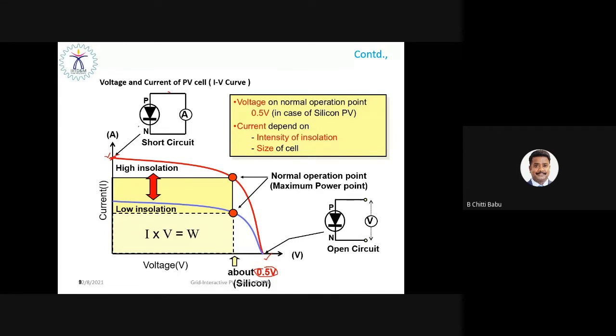All right. Now with change in irradiation or temperature, of course, the characteristic looks like this, right? You can take a particular point, or the tangent, where the corresponding voltage is the maximum voltage and the corresponding current is the maximum current, right? The maximum current multiplied by the maximum voltage gives the maximum power that we are extracting from the solar PV. This point is always moving upwards or downwards with change in irradiation and temperature, so you have to apply a kind of control circuit between the PV panel and the load so that this point remains in equilibrium at any stage, whatever the change in irradiation and temperature. That is why we employ an algorithm called maximum power point tracking, right?